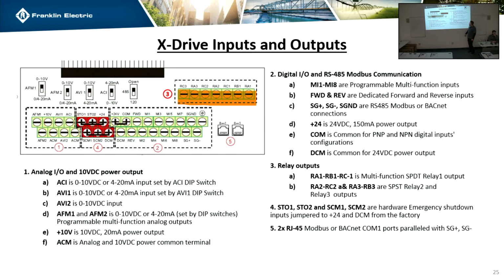The outputs: we have the multifunction single pole double throw relay, and the double throw is going to be dedicated to, well, it's not dedicated, but it's defaulted as your fault relay. So you'll have a normally open and a normally closed fault relay by default, and then we have two other single throw relays that are multifunction, and we'll go through the list of all the options.